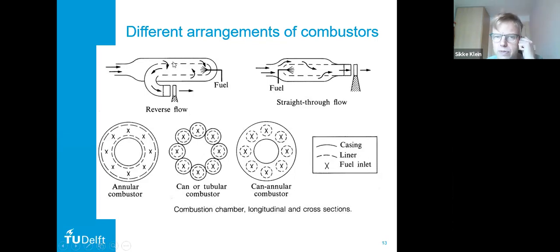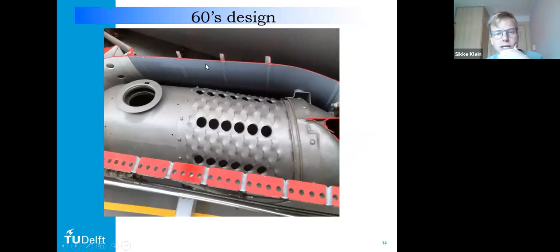They're actually only used for cooling. So only part of the air goes to the end of the combustor where the combustion takes place. On this hot end of the combustor you have less air, and air is gradually added, so you cool down until you reach the right turbine inlet temperature. By not adding all the air at the fuel, you can create a hotter, more stable zone here, and then adding the air later on, you get the right turbine inlet temperature. So that's the reason they do it, by not adding all the air for the combustion. And you see it here, these are called the dilution holes. So only part of the air goes to the combustor, and the rest is added more downstream via dilution holes.